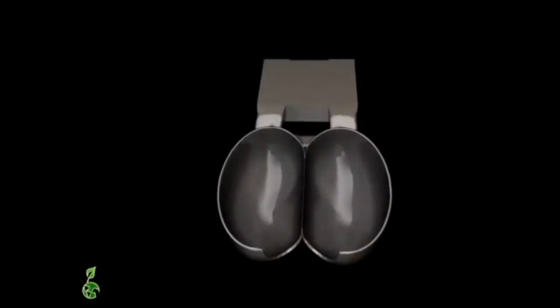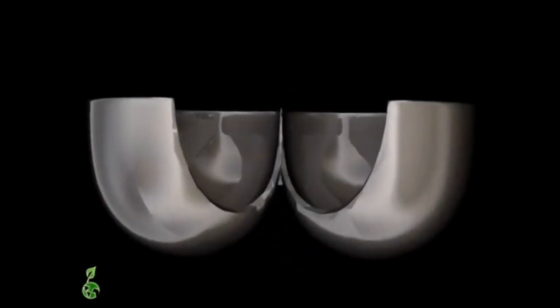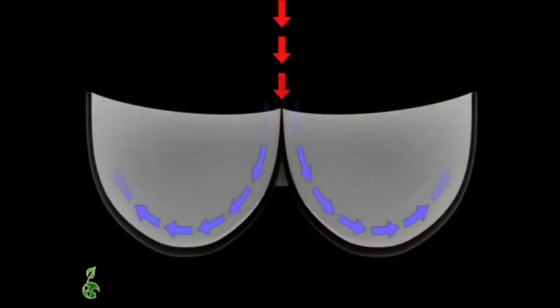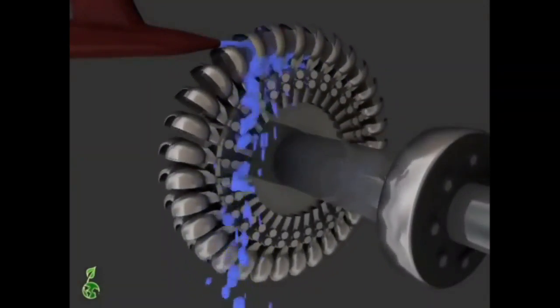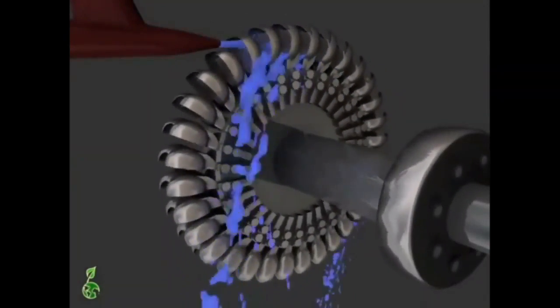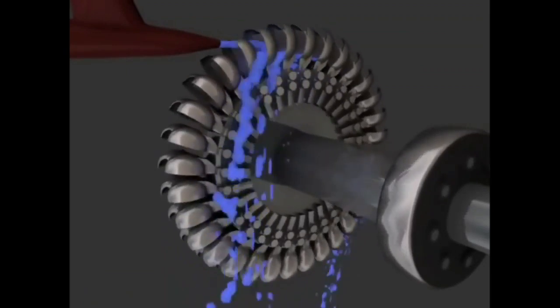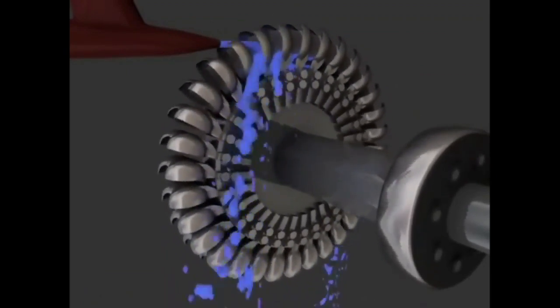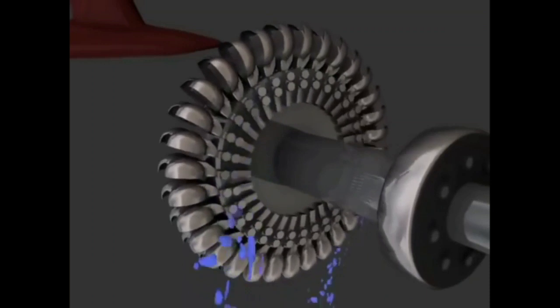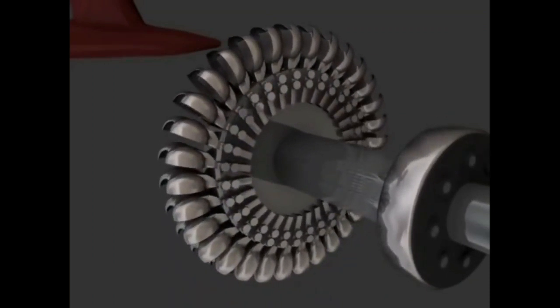We have the splitter here at the center. The water will be striking the splitter, which is at the center, and which divides the water, or jet, into two equal parts, and the water will leave the vane, deflected at an angle of 160 to 180 degrees. Because of this striking of the jet on the bucket, the runner will rotate, and in turn the shaft will rotate.